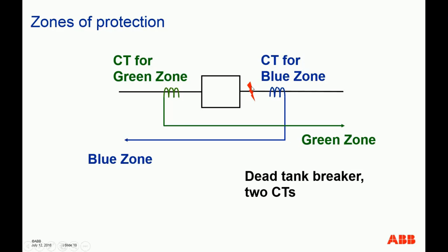Because the breaker is open, there's no reason for this blue zone bus protection to operate, because you actually unnecessarily interrupt the service of the load on the left-hand side of this slide. So modern relays, for example, have a solution for that. For example, once you see this breaker is open, you can actually tell the relay. Of course, this type of algorithm has been designed into the relay.